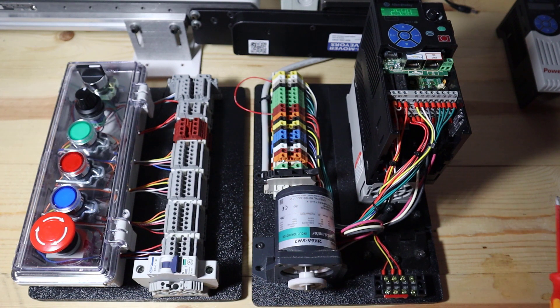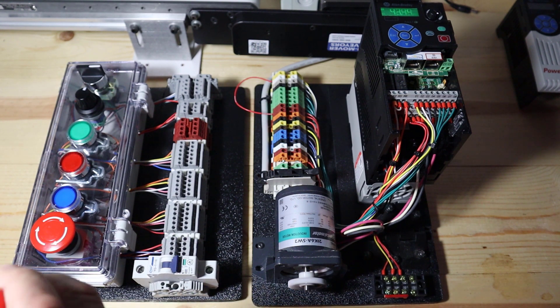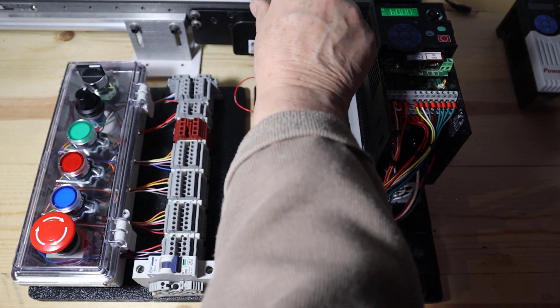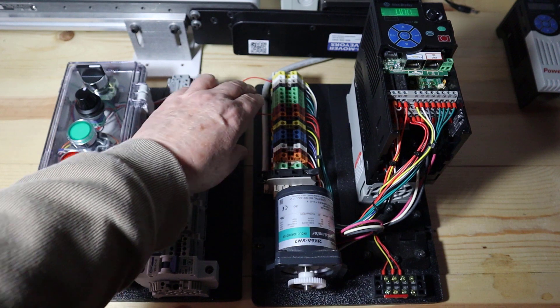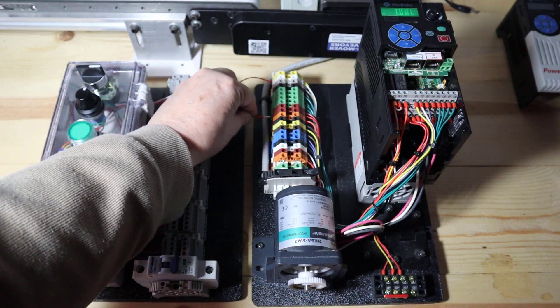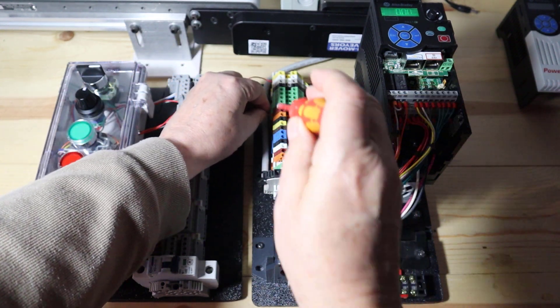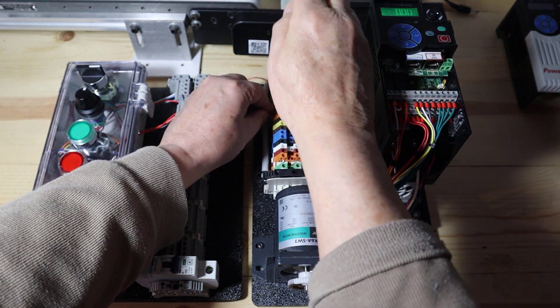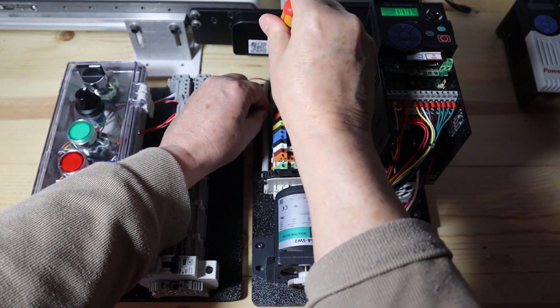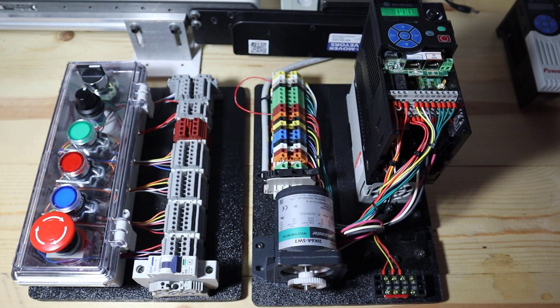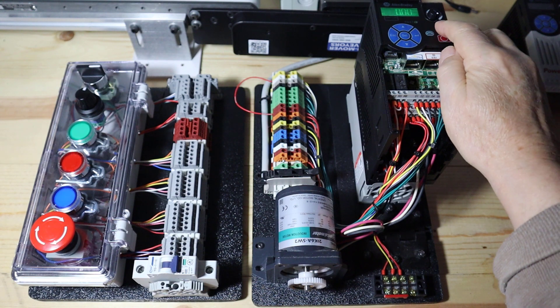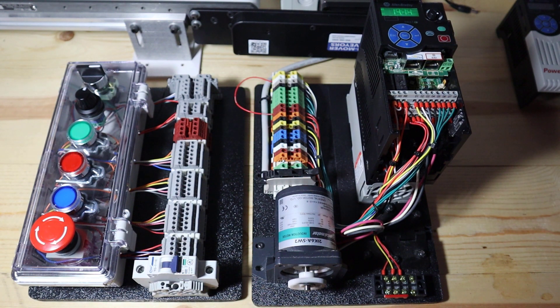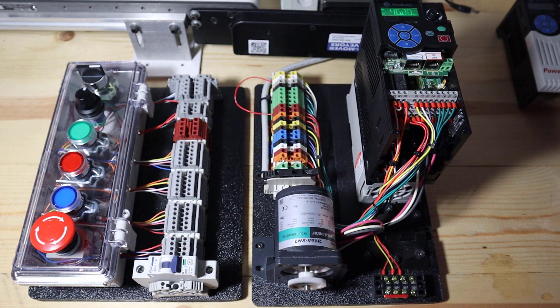So if you look down at the bottom you can see the wheel turning. If I increase the speed you can see it ramp up, so I turn it all the way up to 60 Hertz. And if I hit the stop button you'll see that it's slowing down, ramping down to a stop. Start it back up. Okay now I want to remove the jumper. Now watch what happens when I remove it, it's stopped. If I put it back in it doesn't start back up, we wouldn't want that because we wouldn't want the drive to run the motor just because that jumper is in. So we hit the start button and it starts back up again.